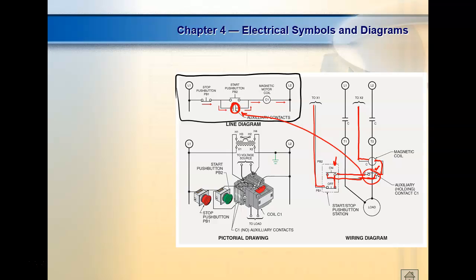Well, we come up here and number the wires. We may call this wire 1, wire 2, wire 3. This is still wire 2 because it's electrically the same. This would be wire 3, this right here would be wire 4. So your wires would be numbered if you wired it up—you should number them, so anything connected together gets the same number.